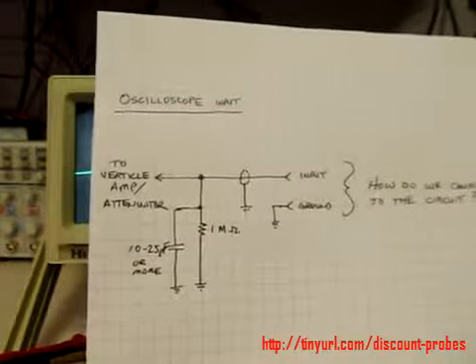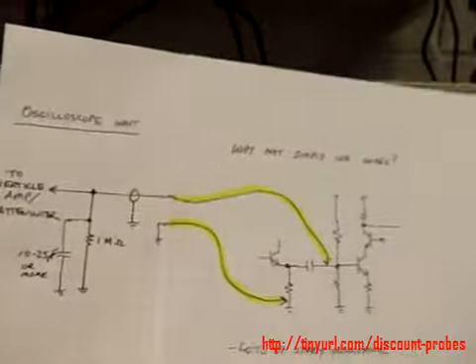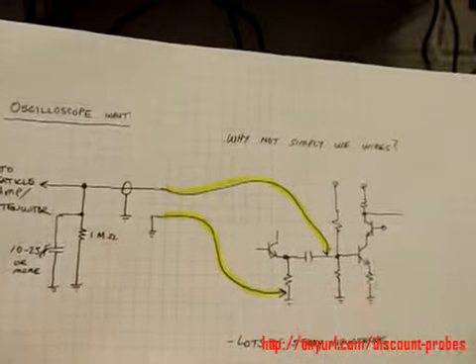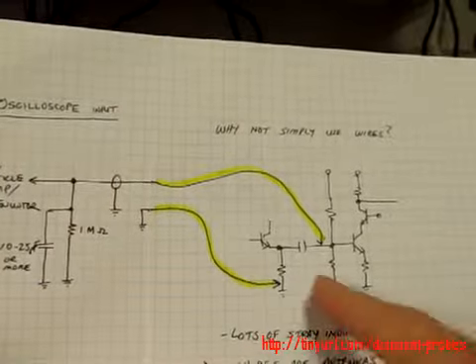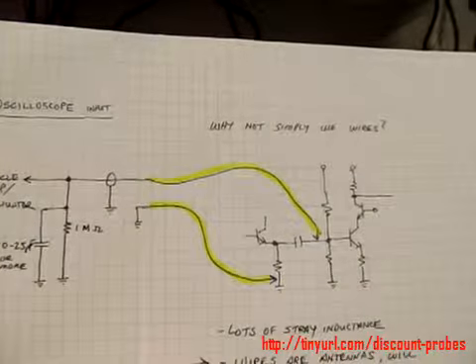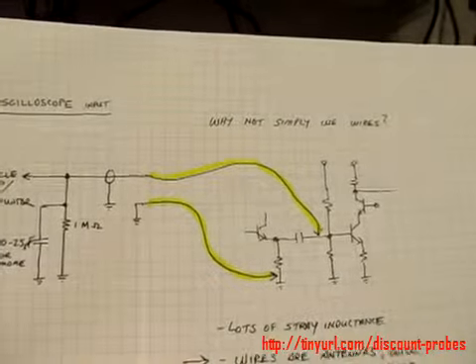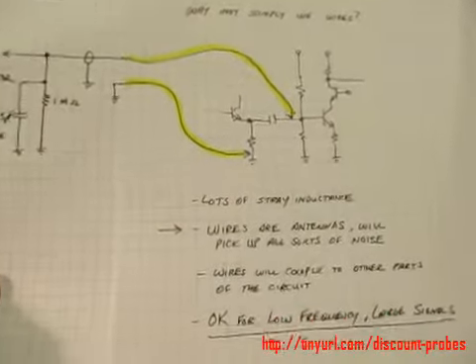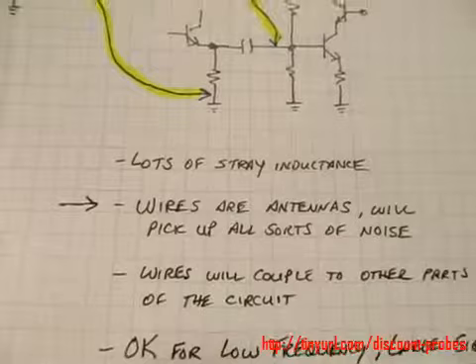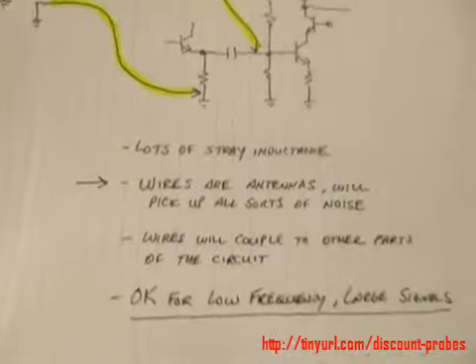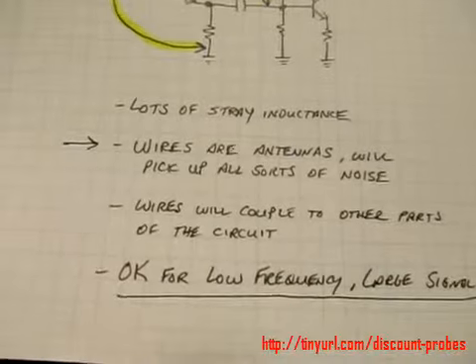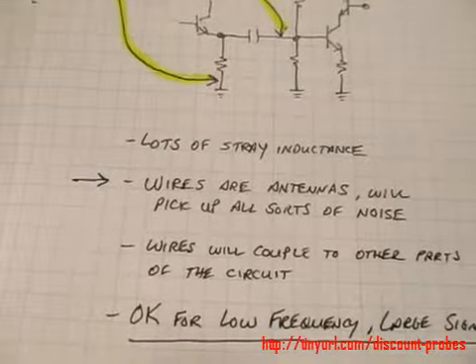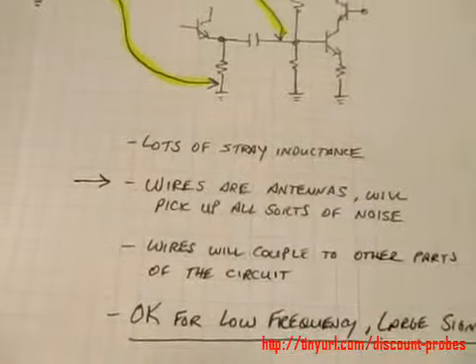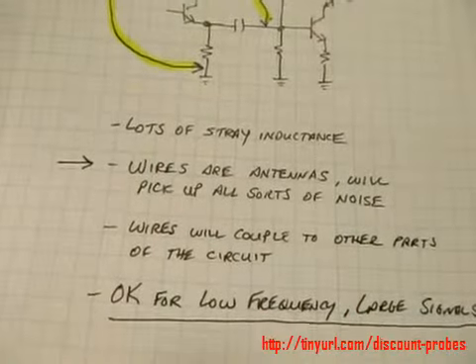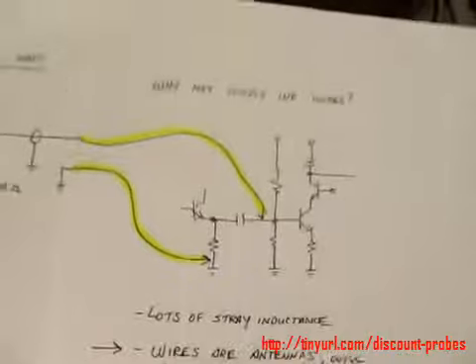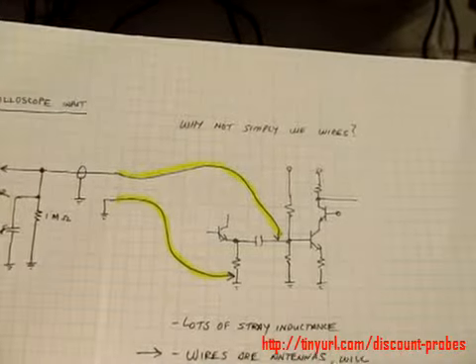So if we just connect up the wires like we just did, this is what happened here. We connected up these wires. They basically look like big antennas, okay? And so even if we connect it up to a circuit, if the circuit's not low impedance, you're still going to be injecting noise into your circuit, and you're also going to be injecting noise into your measurement, okay? So it works as long as your signals are really low frequency, or you've got some really large signals you're dealing with. Otherwise, you're adding a lot of inductance into the measurement path. You're picking up all kinds of stuff with these wires and they're acting like antennas, and you might even couple some signals to other parts of your circuit. All things that are not really good. So that's typically why we don't use wires.